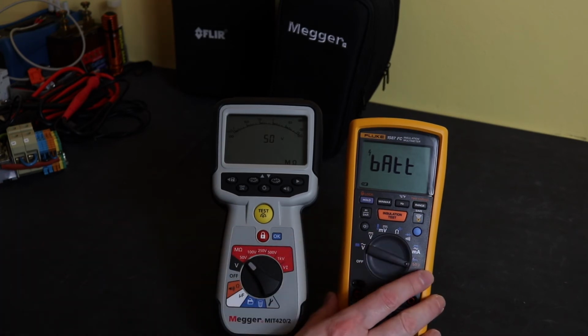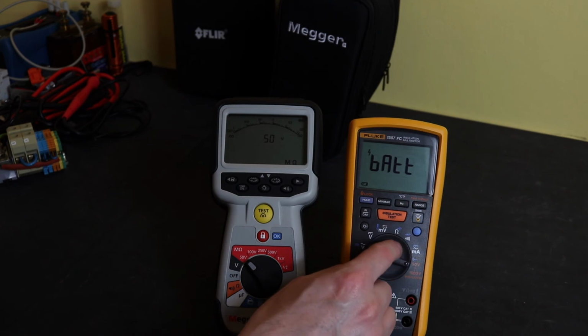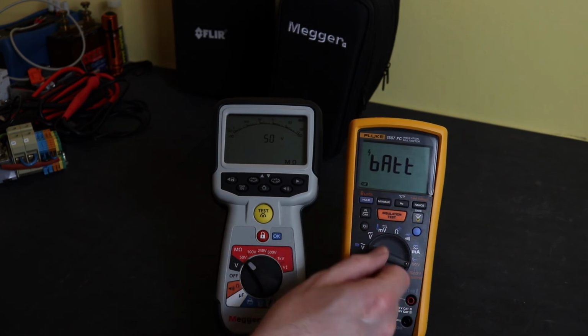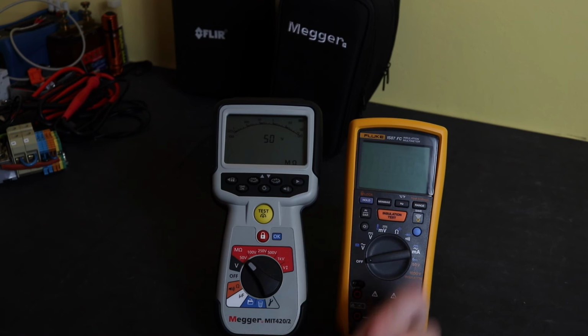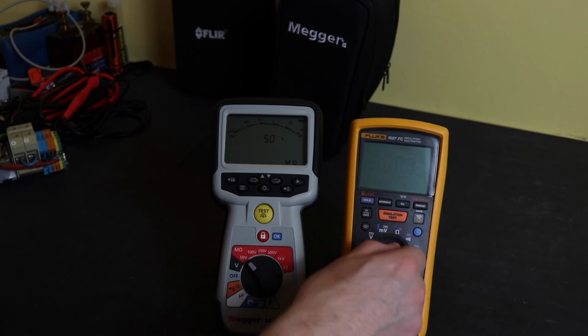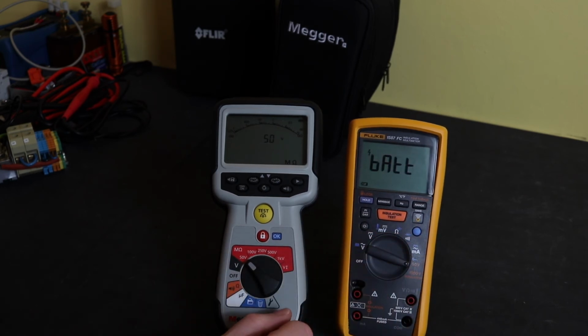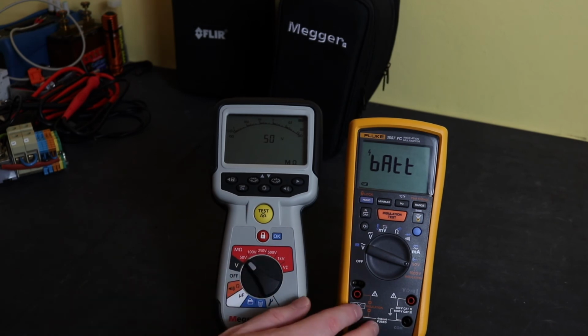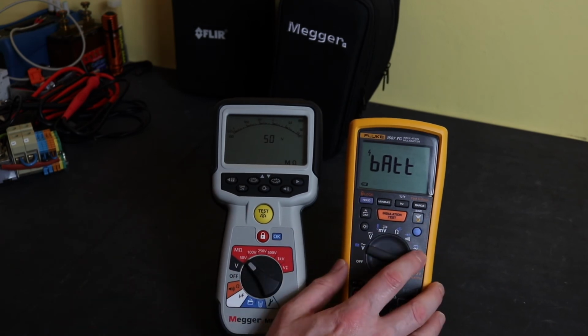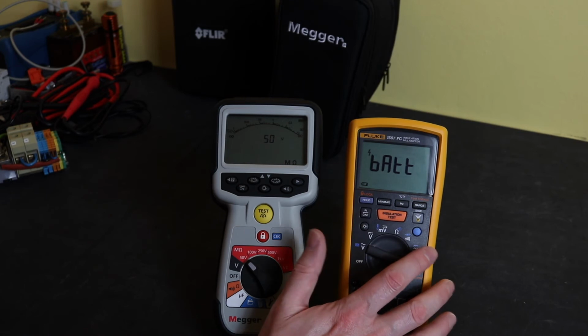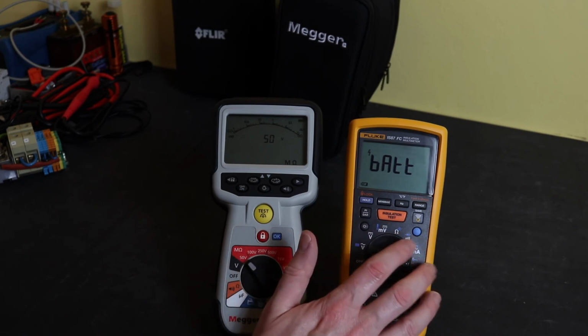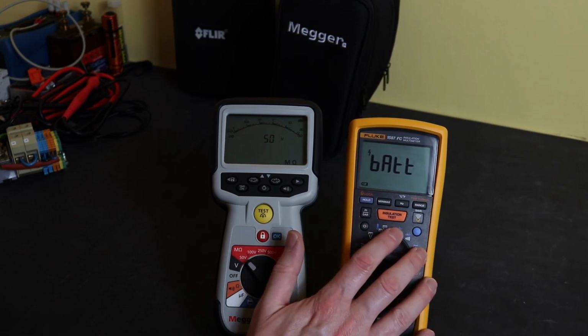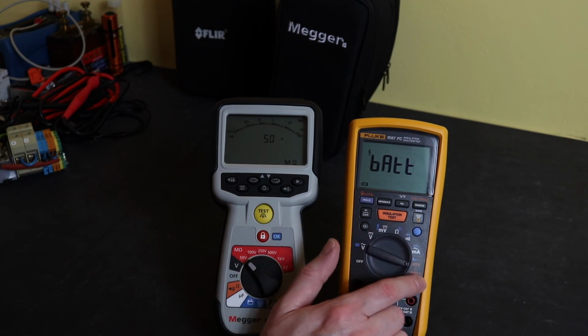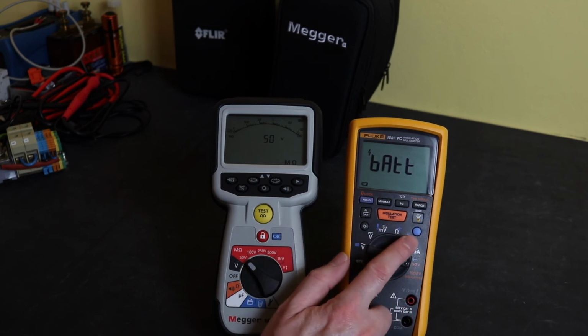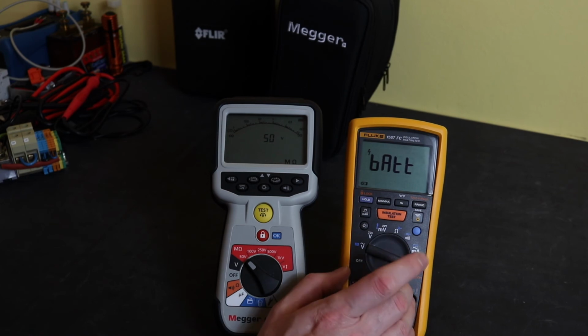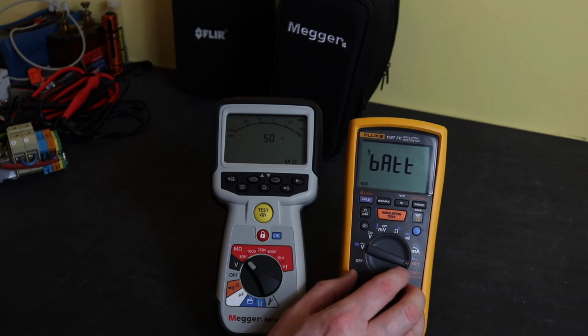For the 1587FC, the test voltage is selected electronically from the range up here, and it won't do it because the battery's gone flat. I don't know if I'll get away with... No, it's well gone on me, hasn't it? Okay, so you just have to trust me, it is exactly the same test voltages, 50, 100, 250, 500, 1 kV on this instrument as well. You, however, don't get the variable voltage, but you do get a smoothing function. Having said that, I don't really use the smoothing function an awful lot.